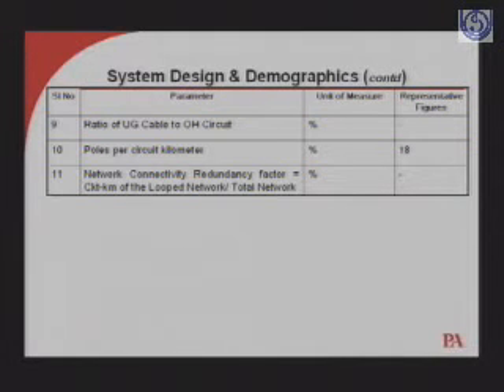Then again, the poles per circuit kilometer. In the rural areas, for 11 kV poles, what's the minimum span length? 70, 80. In urban areas, it is less. It all depends on how much sag we are allowing. There are electricity rules which we have still inherited. The electricity rules specify the sag which we can have on our circuit so that we can decide upon the span length. So it will vary depending on the design practices you have adopted. Then the network connectivity redundancy factor.